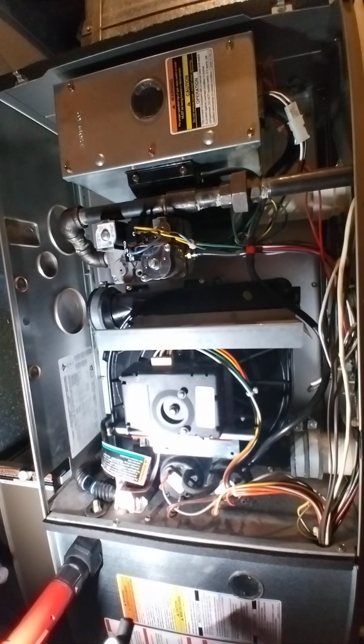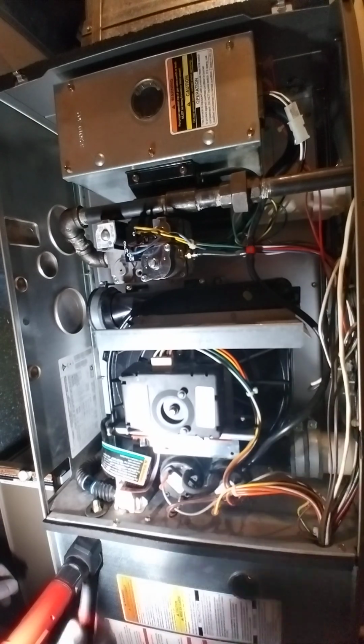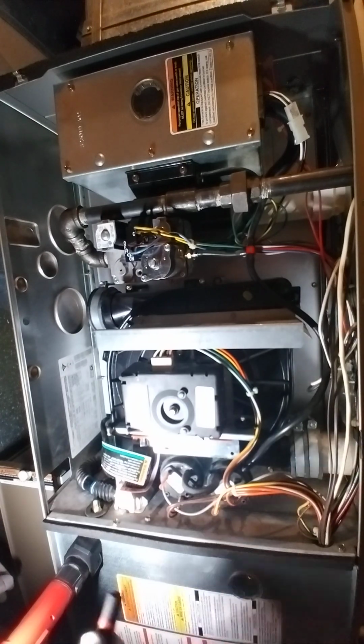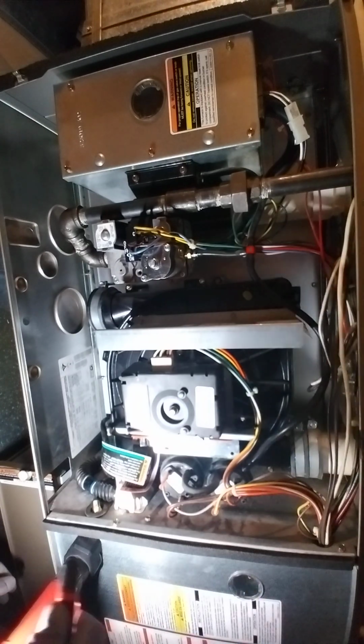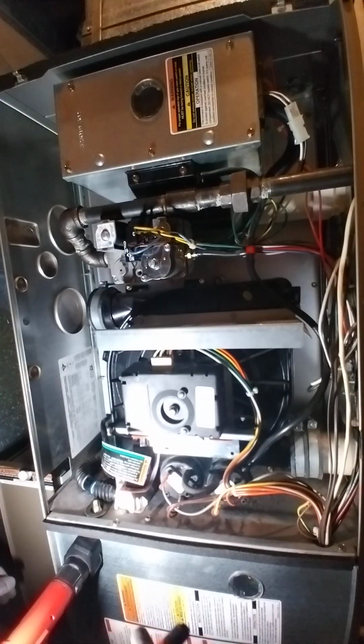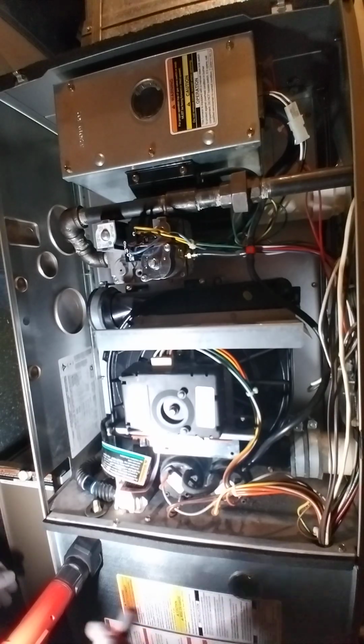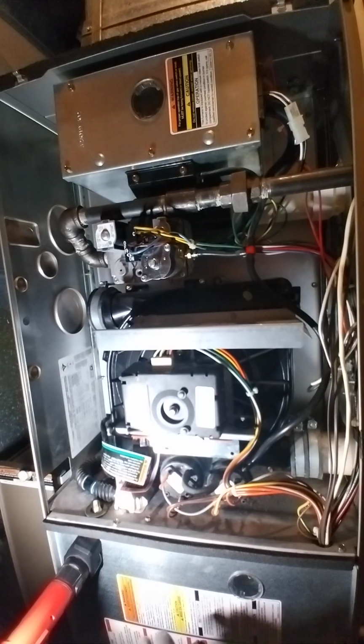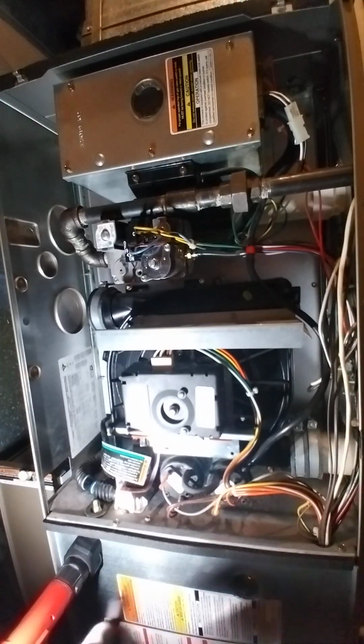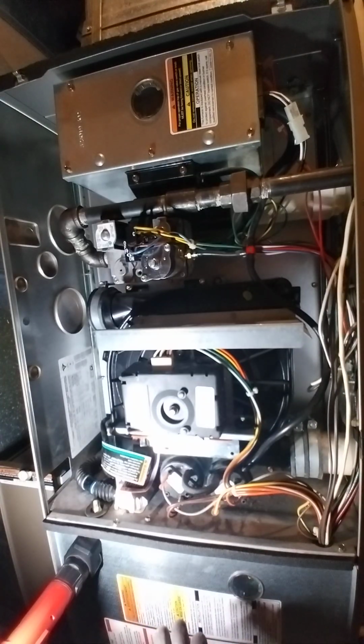So what would happen is it would go from low heat to high heat in the morning, and what it should be doing is then going back to low heat mode after high to finish off the cycle and ultimately stop. But what was happening is it would run in low mode without any problems, and then when it went to high, it would run for about a minute or so, a little inconsistent between a minute and 2 minutes, and then it would immediately stop.